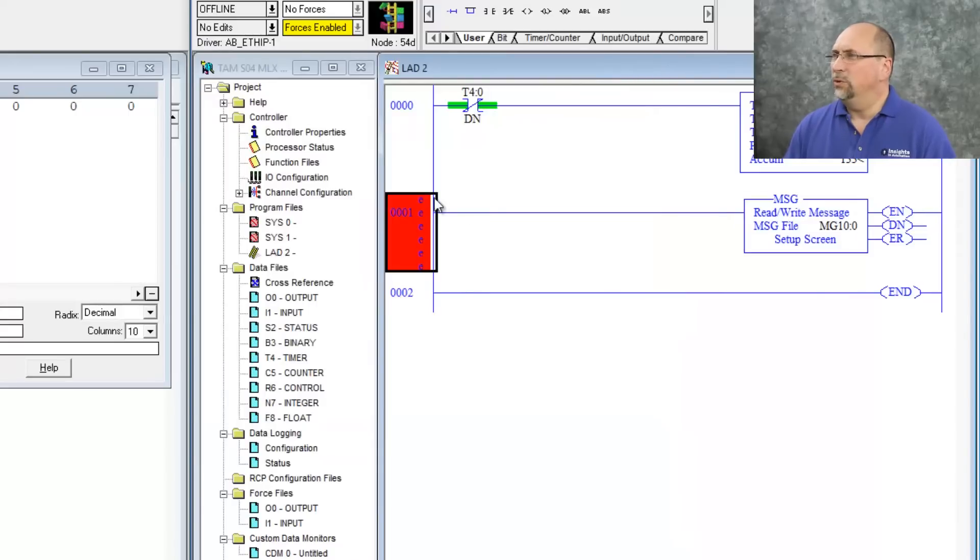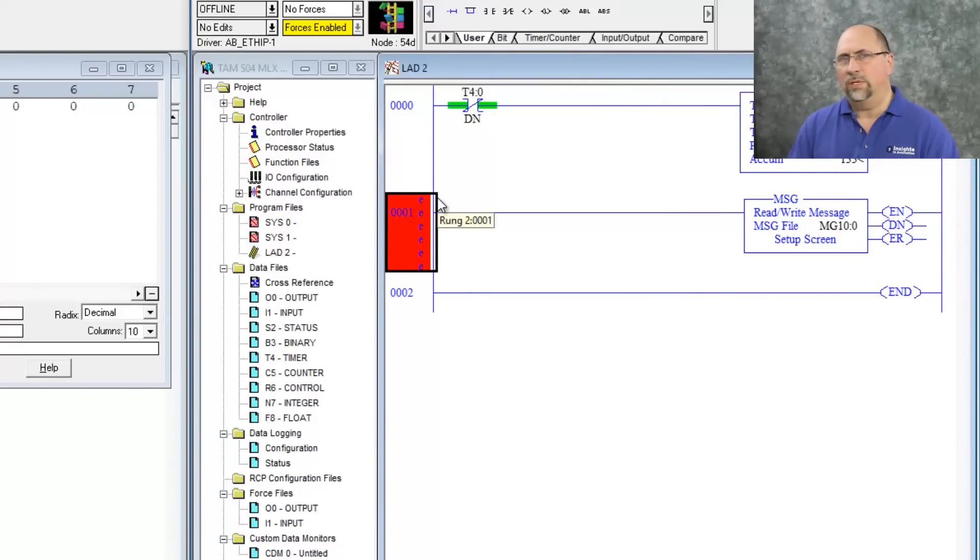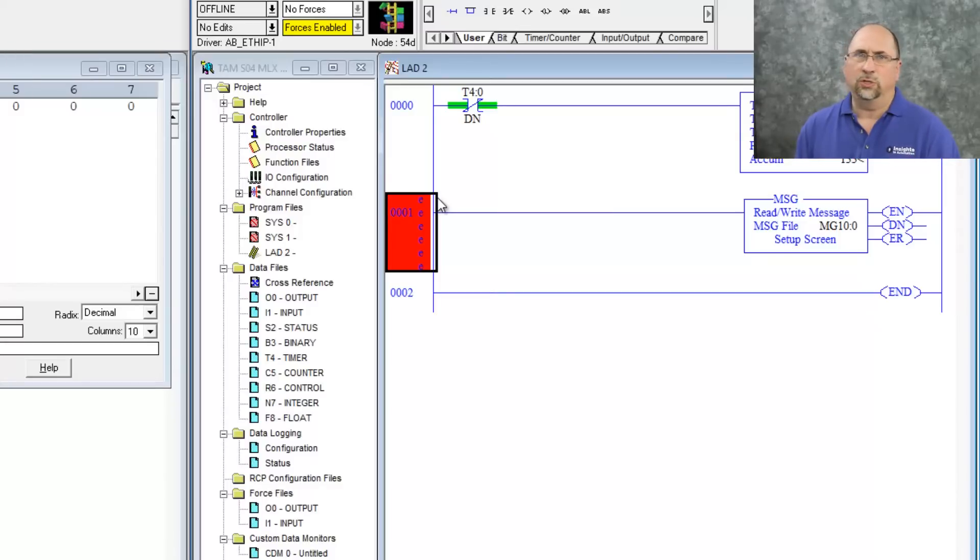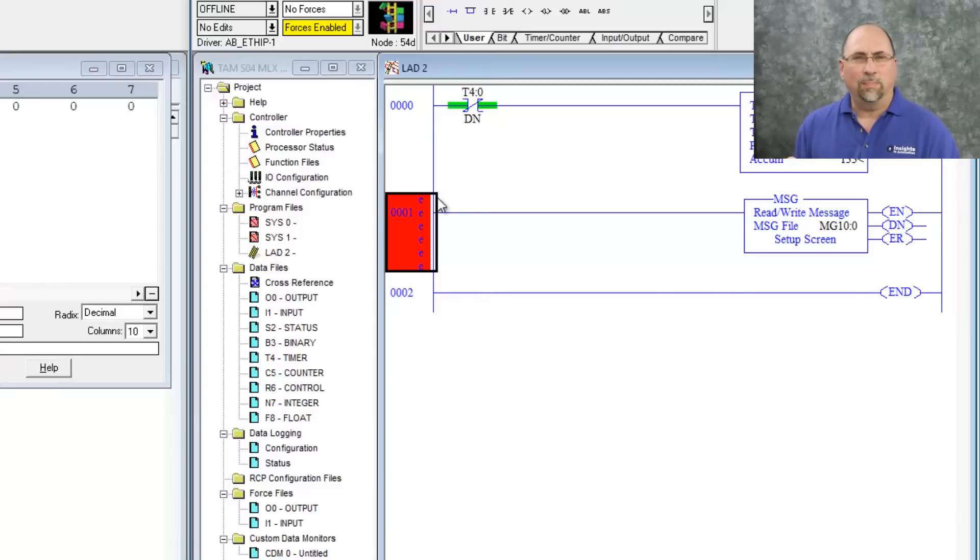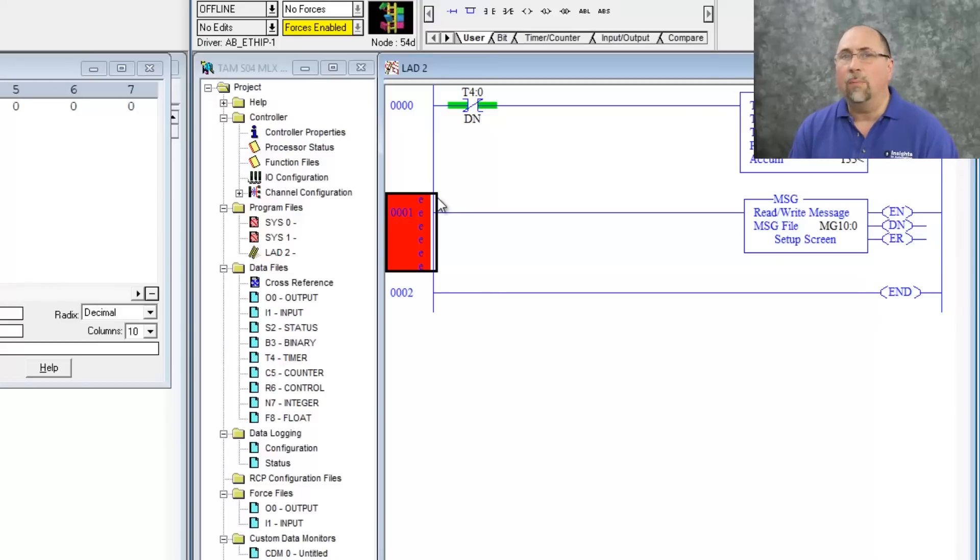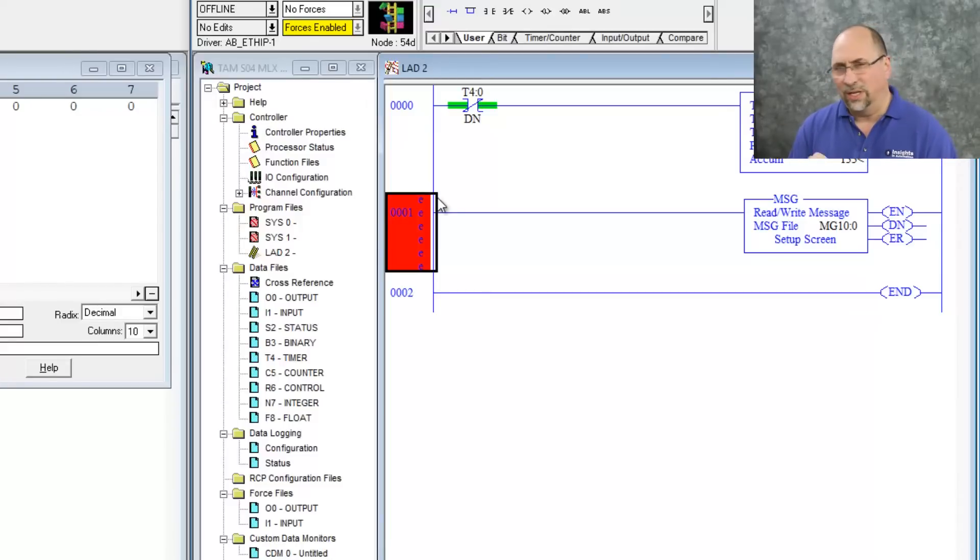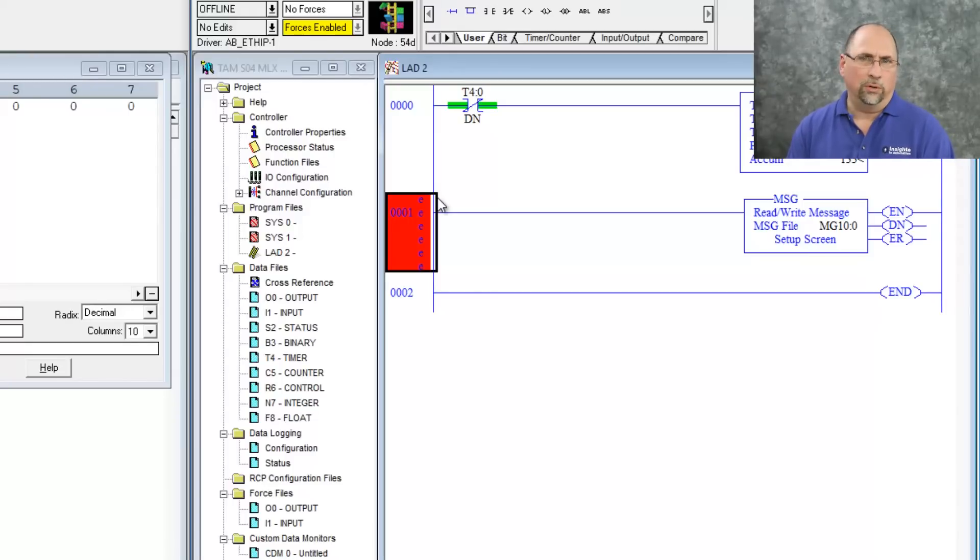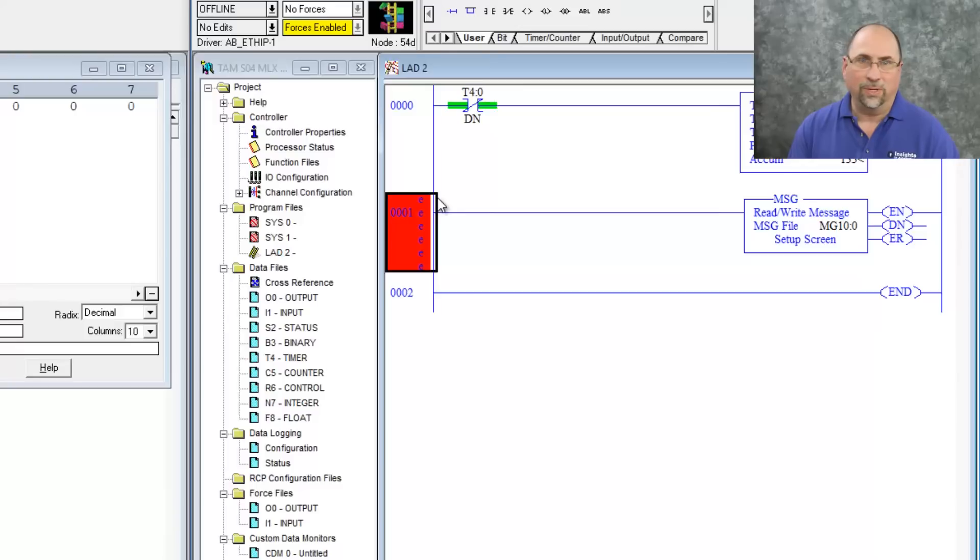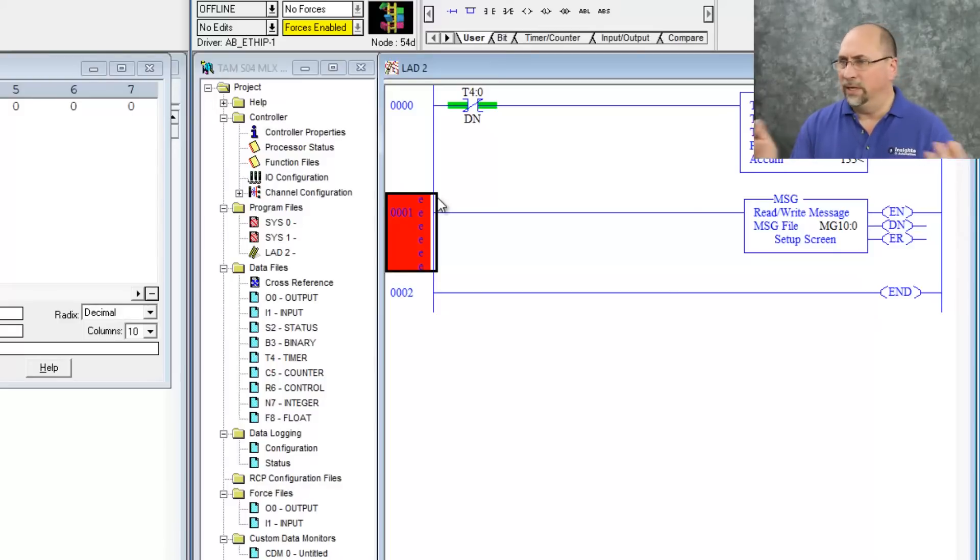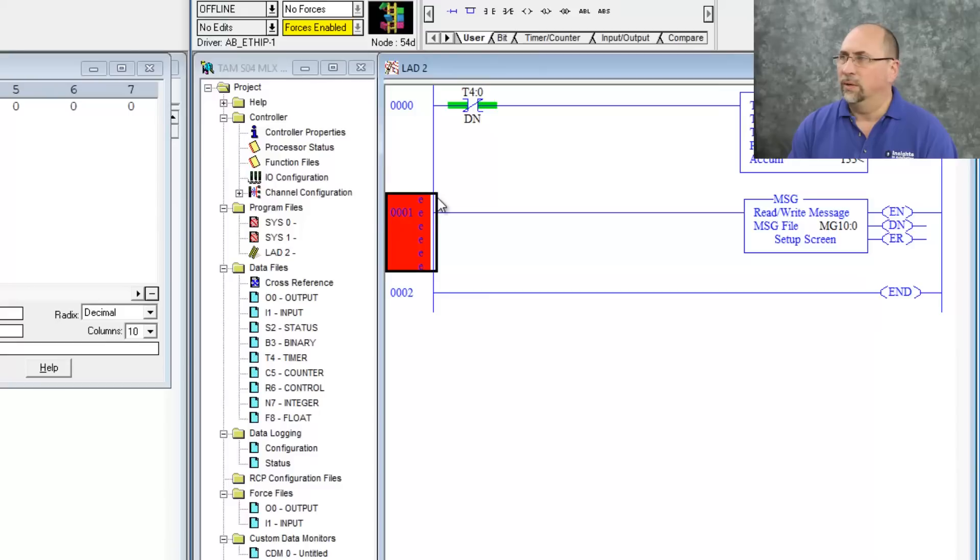I do want to trigger this because the MicroLogix 1400 doesn't have unlimited communications bandwidth. In other words, you cannot issue a hundred message commands at the same time and expect them all to go out. It has a buffer. So you get 10 to 15 different messages you can do before that buffer fills up and you'll start losing messages. Now that buffer limit is dependent on the controller you're using and the port you're messaging out of. But in any case, you cannot send a hundred messages at the same time and expect them all to get processed. They won't. The buffer will fill up and then anything over the buffer limit will be lost.